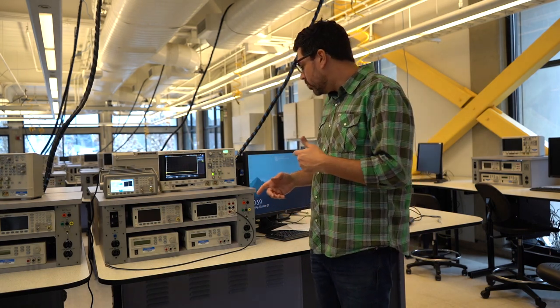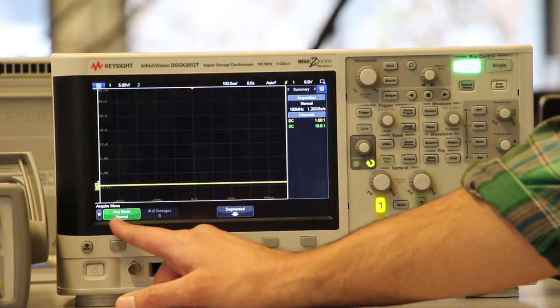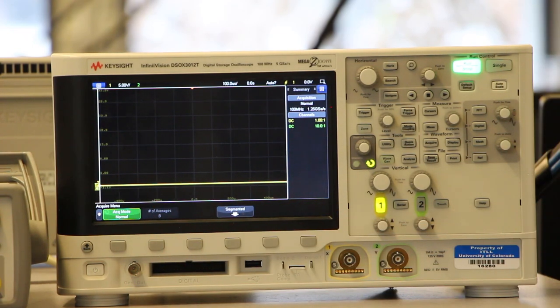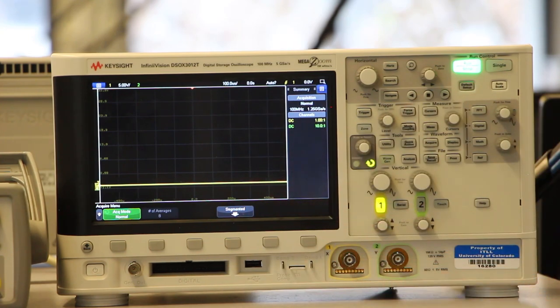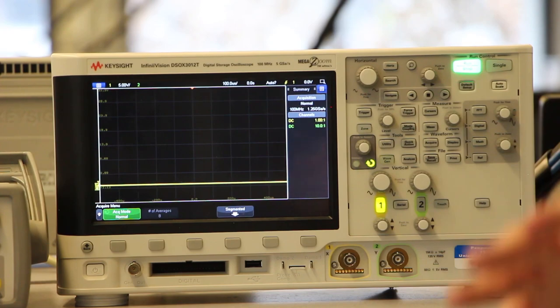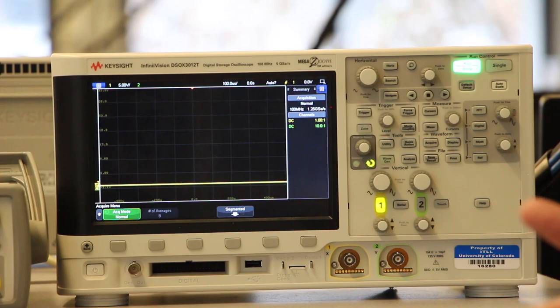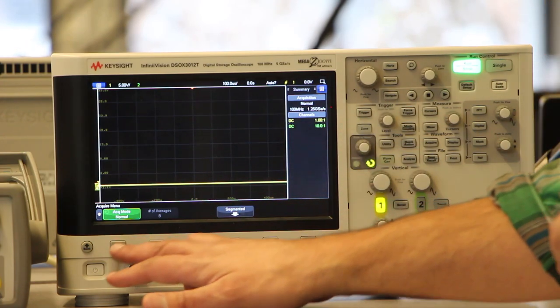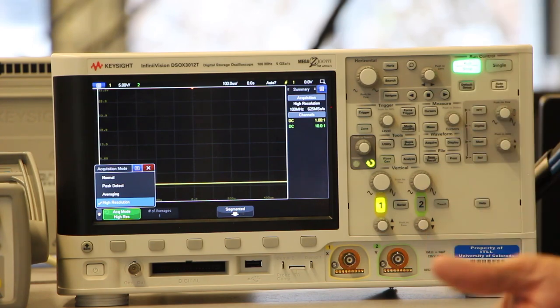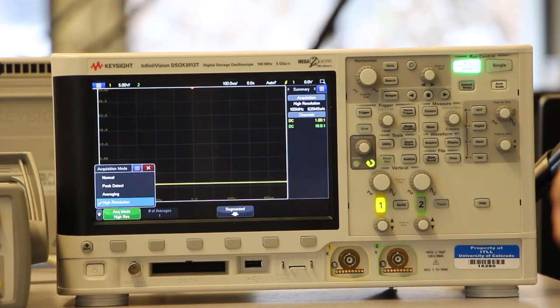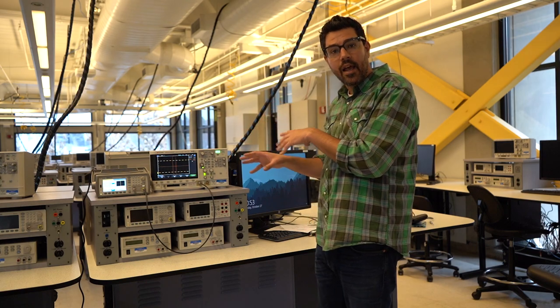Now I want to set up the acquisition mode. All right. So let me show you what that is. If I go to waveform and acquire, you'll see that there's an acquire mode. Now normal is a great option. It's going to collect everything and display everything, both the signal and noise that you're going to find in there. So that's great. But a lot of times you don't want the noise. You want to get rid of the noise and you just want the underlying signal. That said, sometimes you do want the noise if you want to analyze what the frequency of that noise is. But if you want to get rid of the noise, it's got a great function. You can choose a couple of options. But one of them is high resolution mode. And that filters it quite a bit. I'll let you play with that. But for most experiments using high res is really great. And there's of course other measurement tools that you might be interested in. I'm just highlighting one of them.